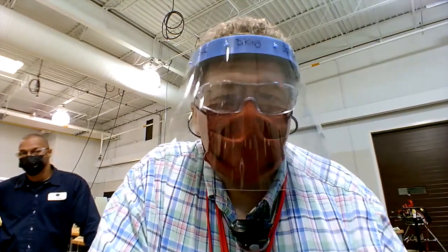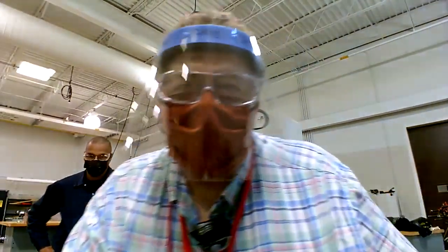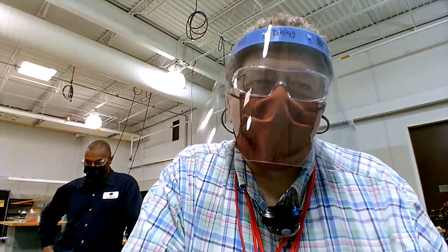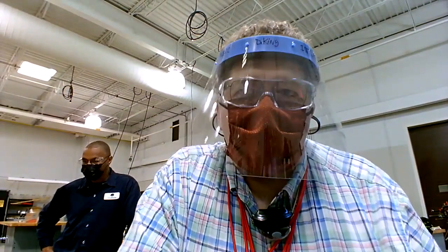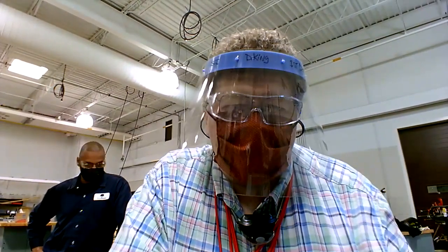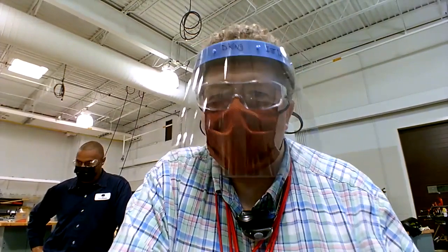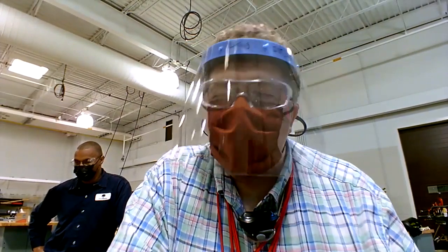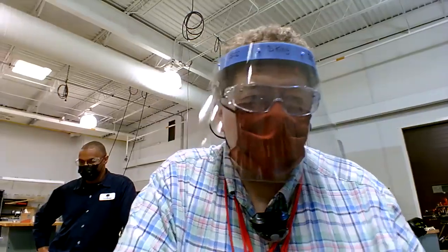So this segment here is going to be on doing insulation tests on motors, how to wire them, how to wire three-phase motors on low voltage and high voltage, and how to do an insulation test to see is the motor bad or not. Is it shorted to ground, or does it have a broken winding on the inside?